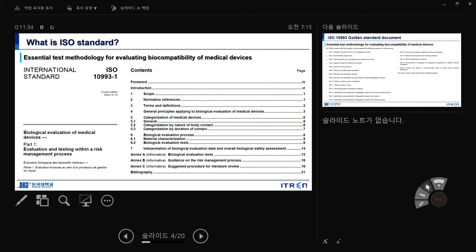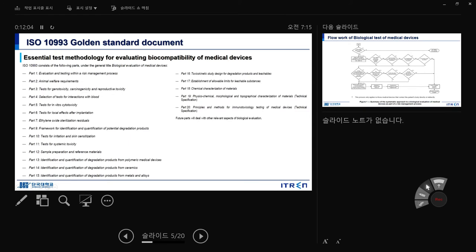For example, ISO 10993-1 is from the 4th edition, launched on October 15, 2010. The index and annexes contain very important information. Especially Annex A — biological evaluation tests — is very important and I will show you later. ISO 10993 is the golden standard document for biomedical device investigation; it is the essential test methodology for evaluating the biocompatibility of medical devices. Let's look at each part one by one.